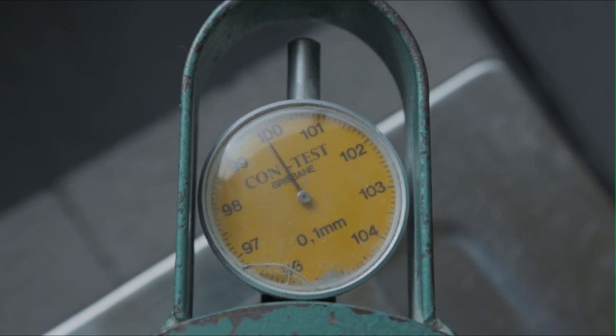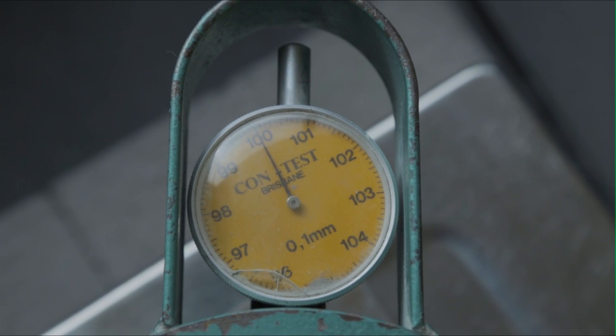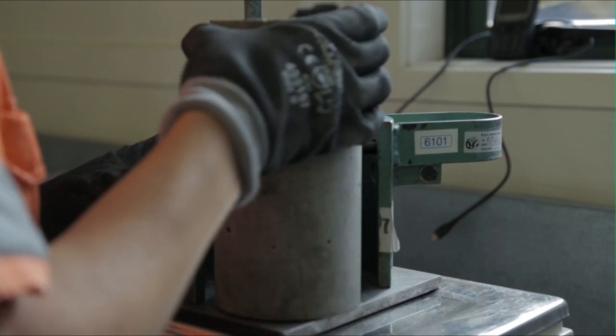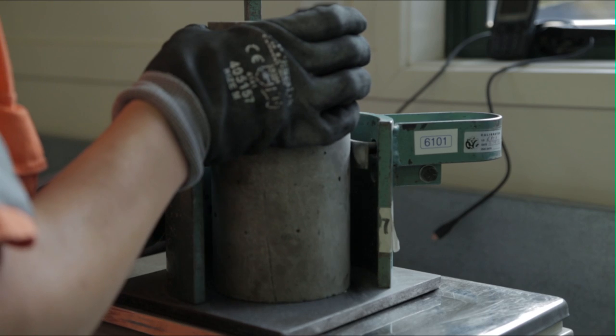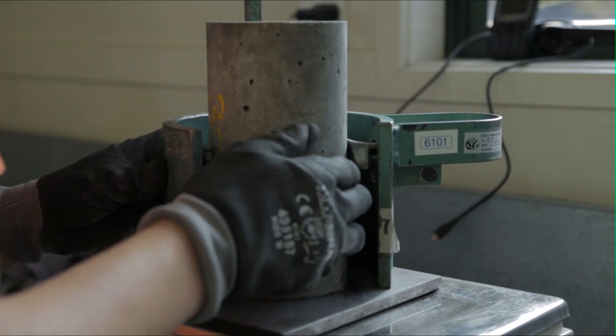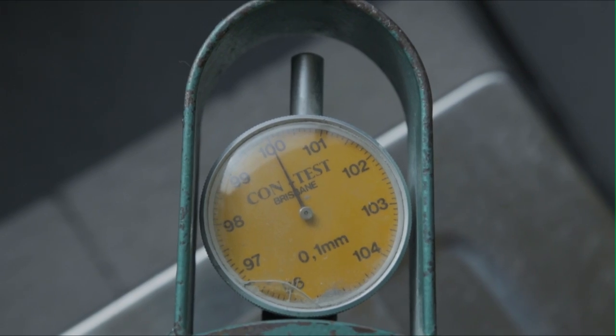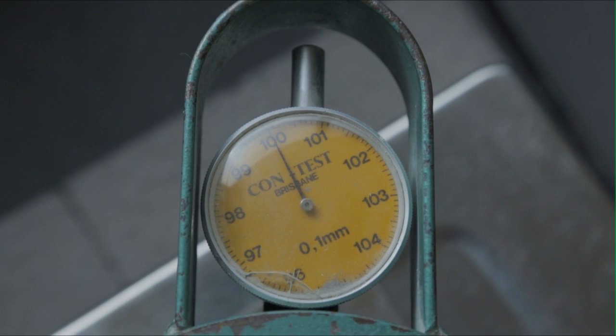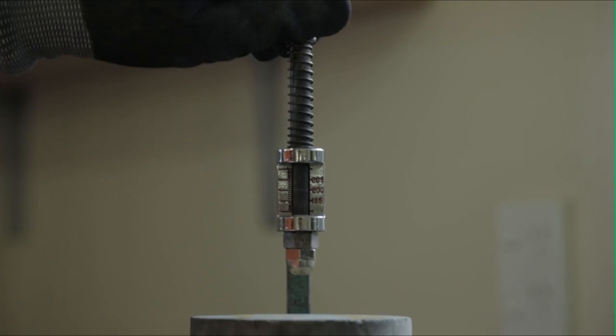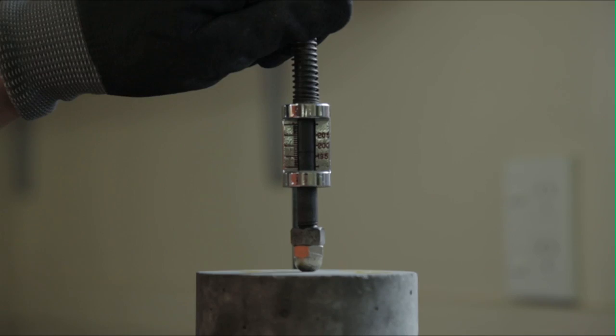Note that achieving the required accuracy of the diameter and height measurements is very difficult using a ruler, and most labs have a specialized piece of equipment to make these two measurements routine as is shown here. Note that these measurements are required by the standard and hence should be recorded permanently.